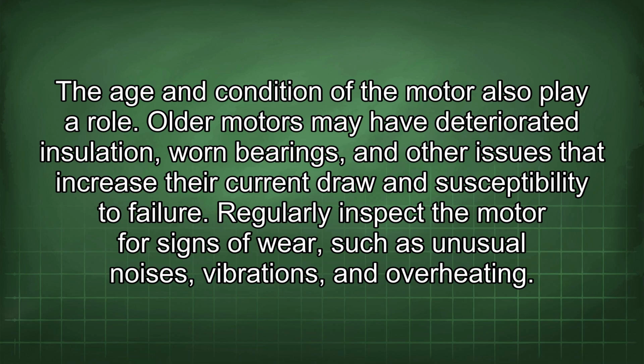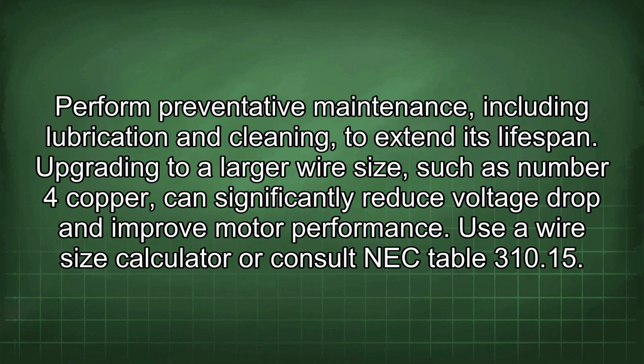The age and condition of the motor also play a role. Older motors may have deteriorated insulation, worn bearings, and other issues that increase their current draw and susceptibility to failure. Regularly inspect the motor for signs of wear, such as unusual noises, vibrations, and overheating. Perform preventative maintenance, including lubrication and cleaning, to extend its lifespan.